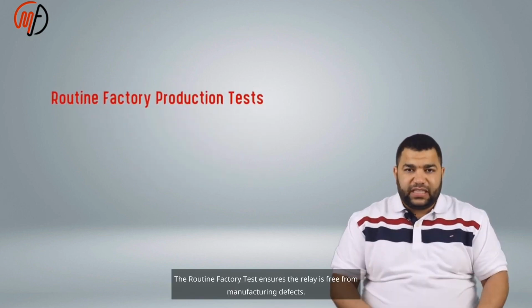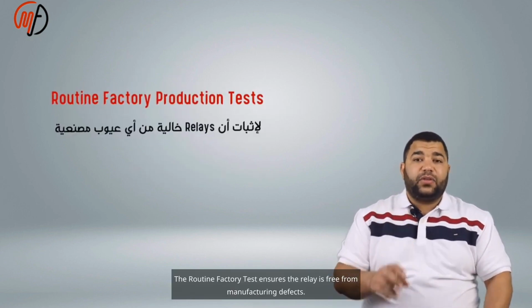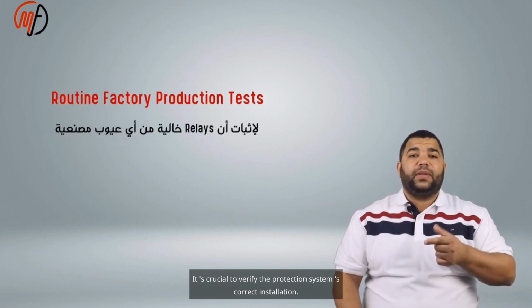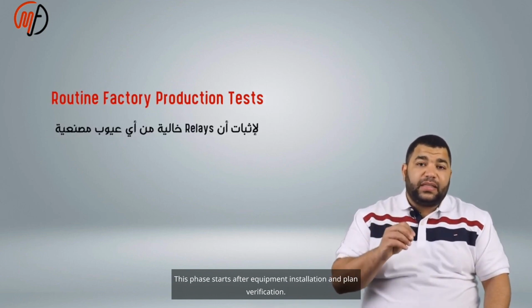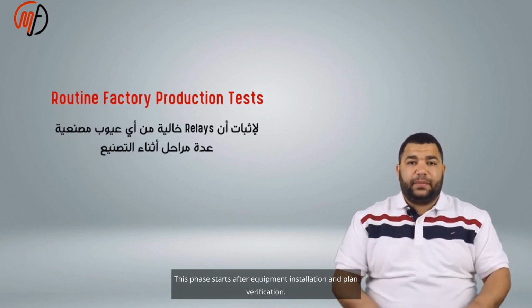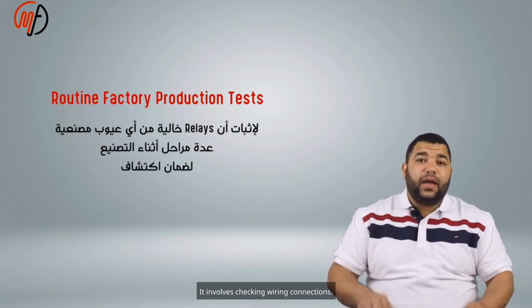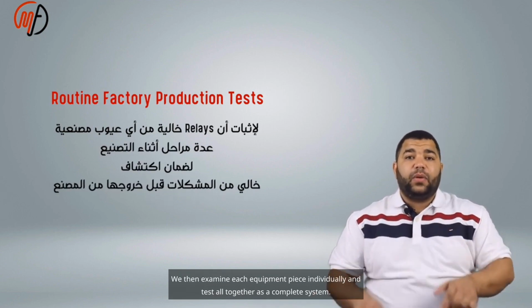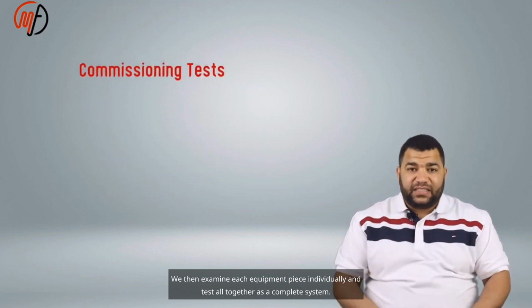The routine factory test ensures the relay is free from manufacturing defects. The commissioning test is crucial to verify the protection system's correct installation. This phase starts after equipment installation and plan verification. It involves checking wiring connections. We then examine each equipment piece individually and test all together as a complete system.